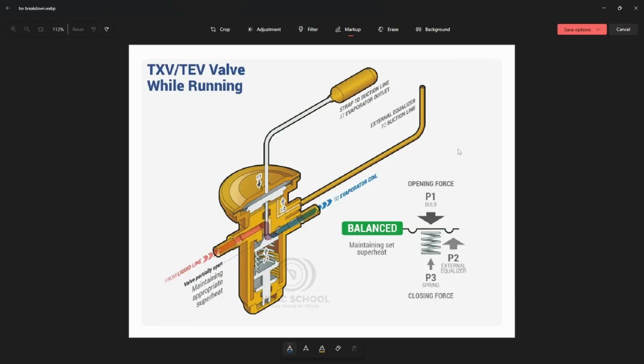EEVs with their response time are also much more efficient, but the downside to them is cost because EEVs have a lot more going on. So instead of us having these pressures and this mechanical device here with a spring and a diaphragm fed by a little sensing bulb, we'll jump on over to our example.